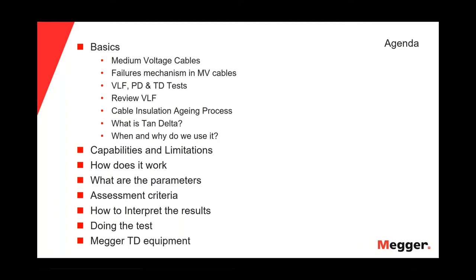So let's start with the agenda. First, we'll go through the basics. We will see the principal characteristics of medium voltage cables. Then we will continue with the failure mechanisms in medium voltage cables. And then we will do a brief review of the VLF test, partial discharge, and tan delta test. Then we will continue with a detailed review of the VLF, and we will move on to the cable insulation aging process, and then we will start to see what the tan delta is, when and why we use it. Then we will see what we can see and what we cannot see with the tan delta, that means the capabilities and limitations.